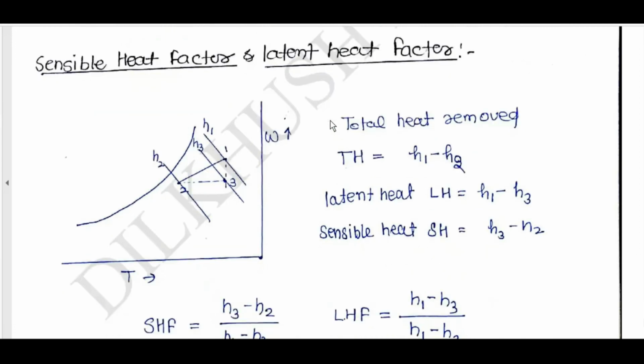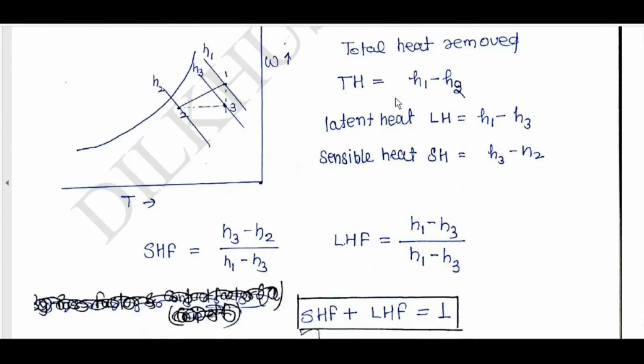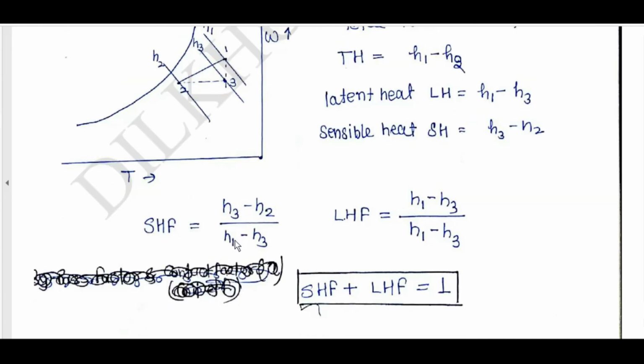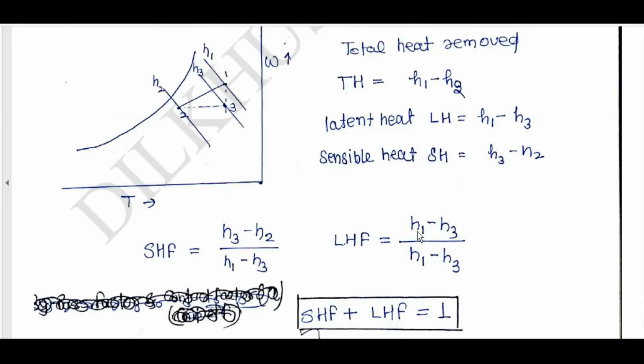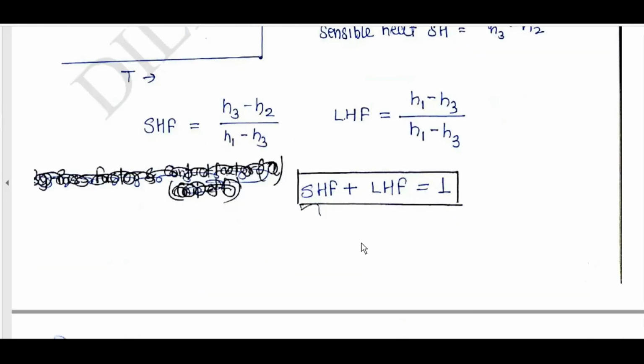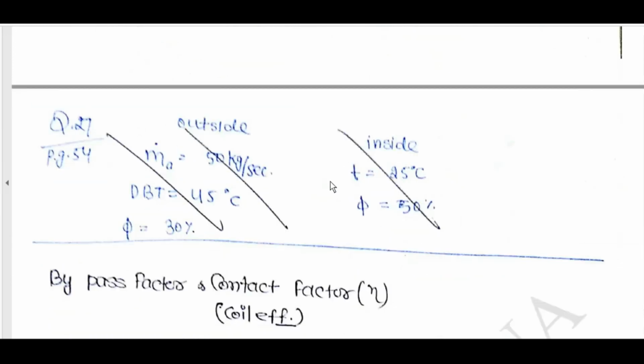Sensible heat factor or latent heat factor. Process 1 to 2, drawn as straight lines. Total heat removed, TH is equal to H1 minus H2. Latent heat, LH is equal to H1 minus H3. Sensible heat, SH is equal to H3 minus H2. SHF is equal to H3 minus H2 by H1 minus H2. LHF is equal to H1 minus H3 by H1 minus H2. SHF plus LHF is equal to 1.